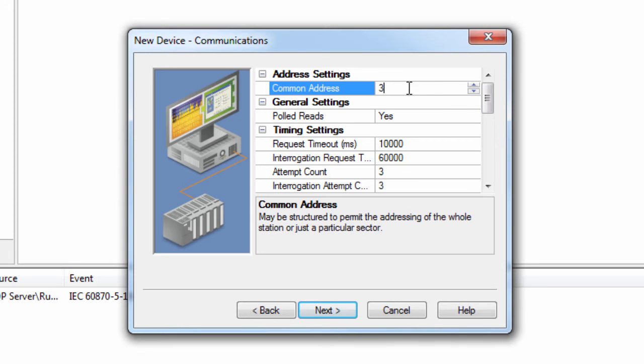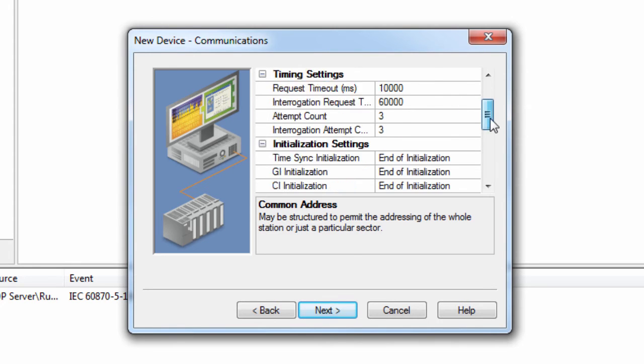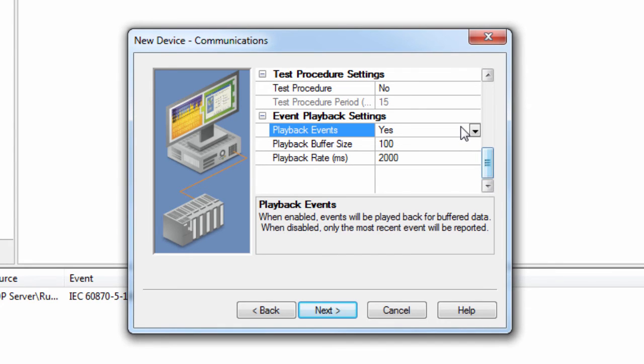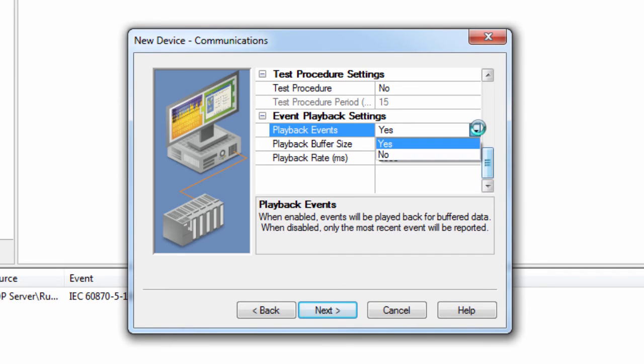Playback Events specifies whether or not Event Playback is enabled. When disabled, all tags associated with Event Playback will report the most recent data, and no data will be buffered. When enabled, events are played back based on the buffer size and playback rate. The default setting is enabled.